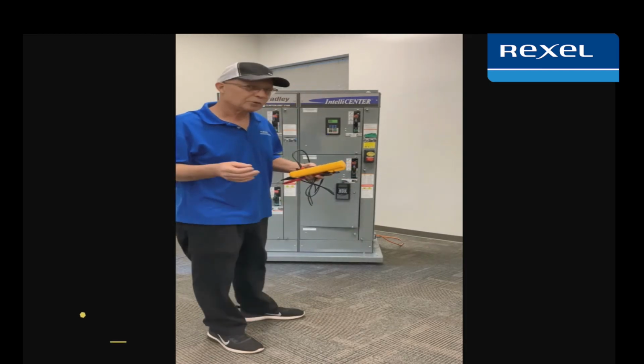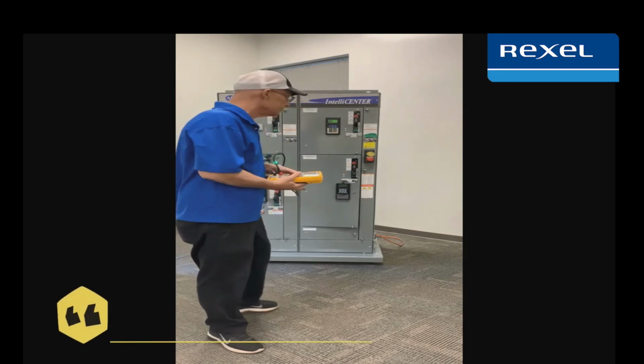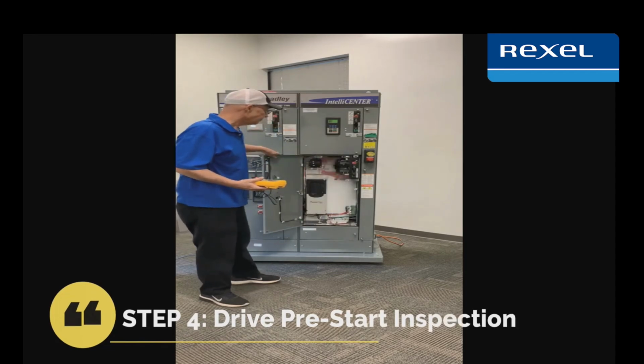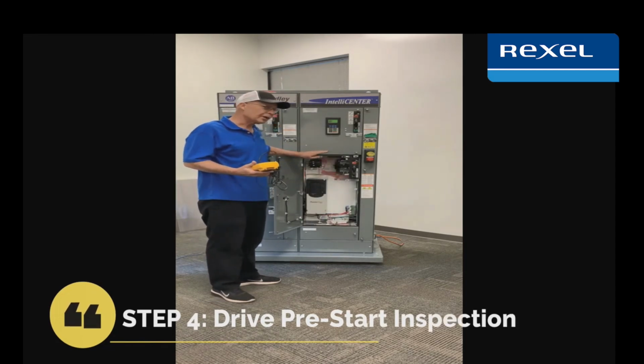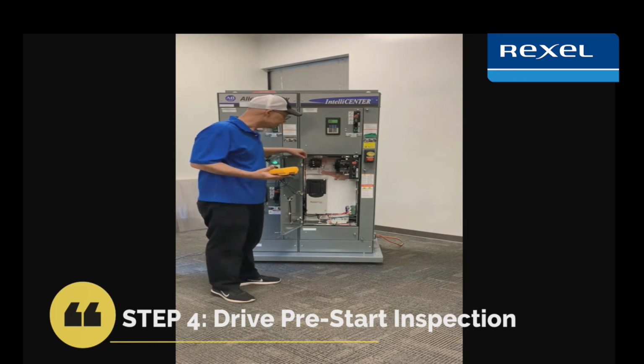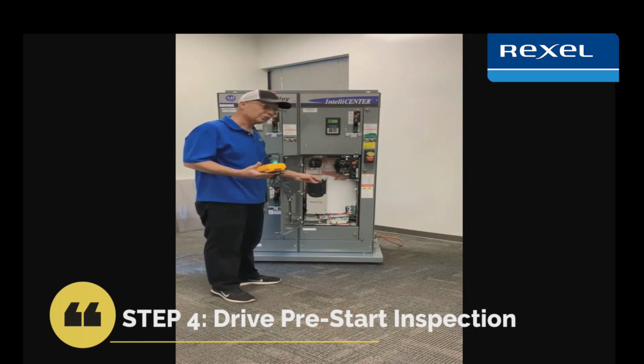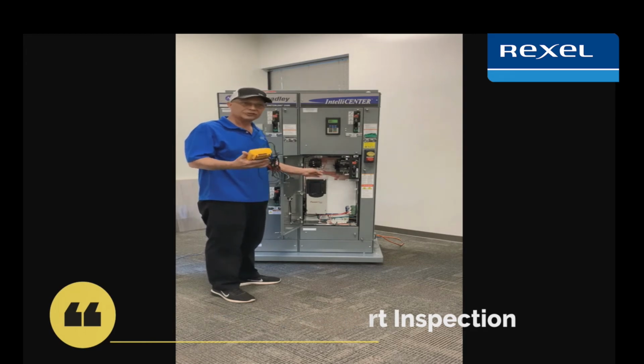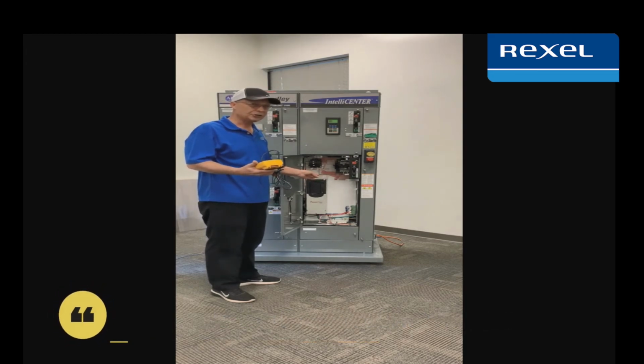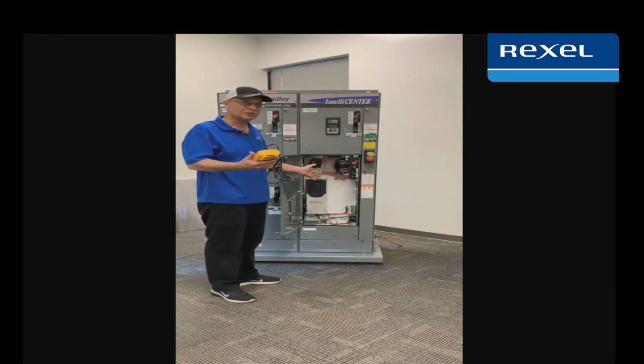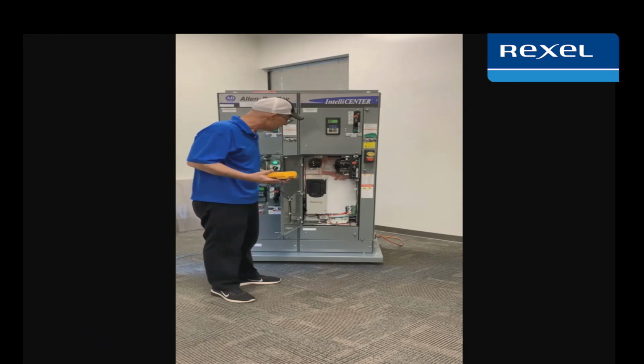The next thing I do is a drive pre-start inspection. And going through this in short, I'm going to validate the circuit breakers and fuses to make sure they don't exceed the maximum ratings of the drive. I will verify the incoming line voltage to make sure that does not exceed the rating for the drive. Inspect the whole wiring in regards to the inputs, three-phase, are installed correctly, and make sure that they're not crossing in regards to any kind of induced voltage or noise.